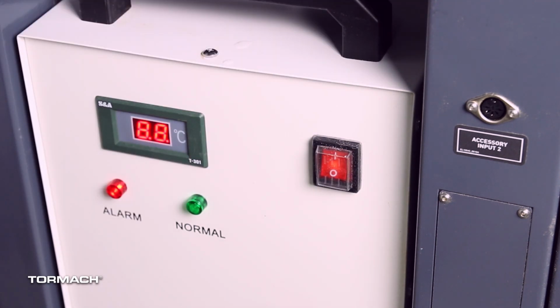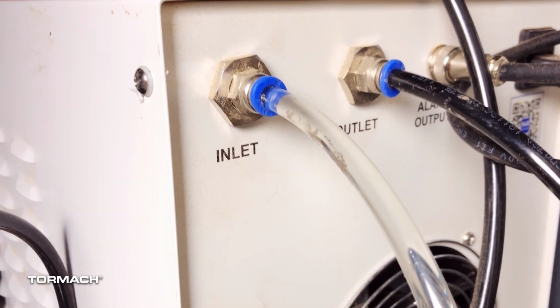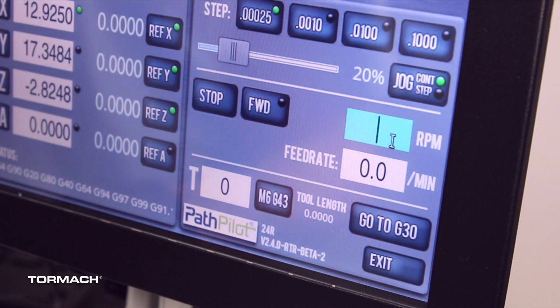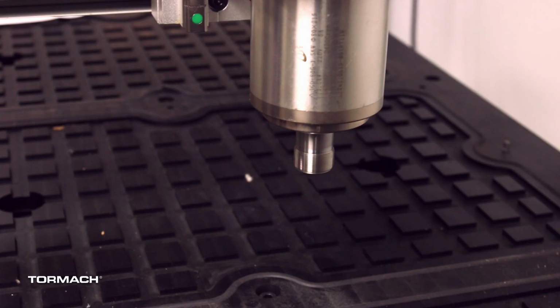Make sure the chiller is on. If it is not, turn it on. And double check that you have water flow to the inlet port. In the RPM DRO field, type 10,000. Then select the Enter key. Select Forward. The spindle should rotate clockwise at 10,000 RPM.